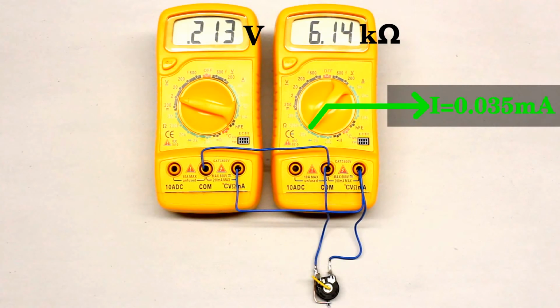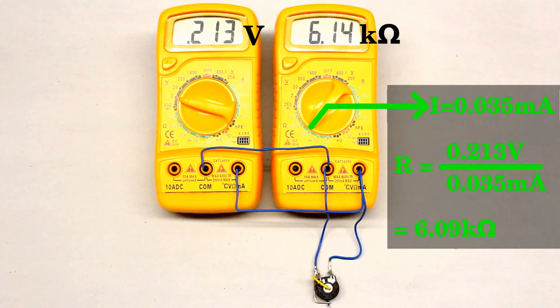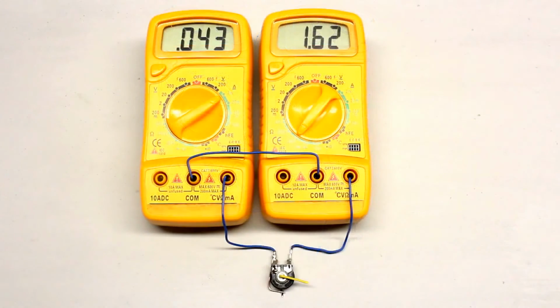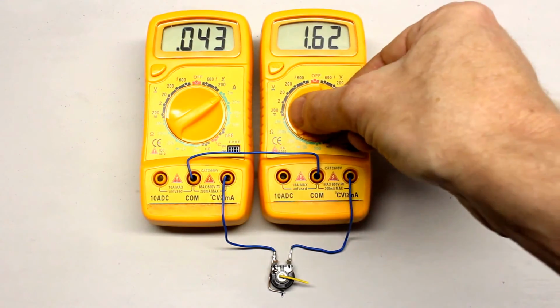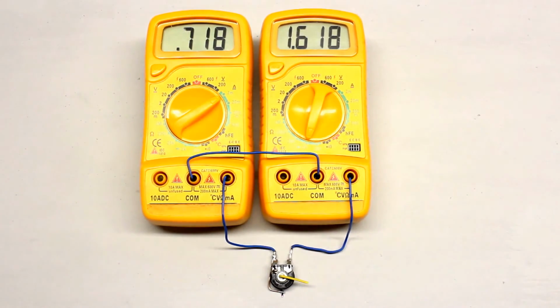A digital multimeter measures resistance by passing a constant current through the device under test and scaling the indicated voltage drop to the accordant resistance value. The magnitude of the current depends on the dialed measurement range. The lower the range, the higher the current passed through the device under test.